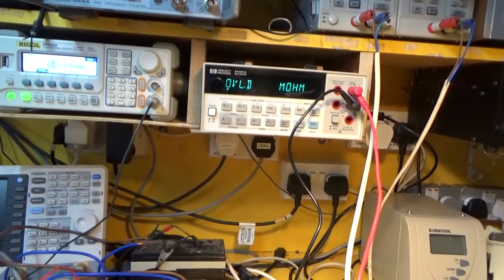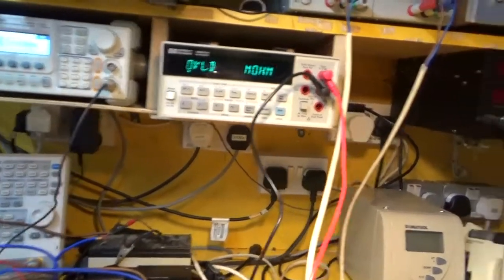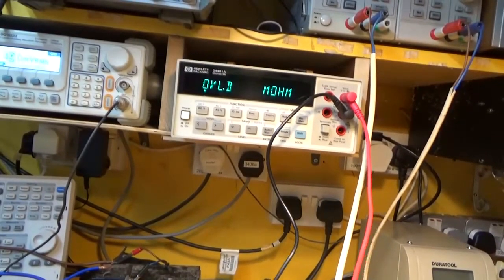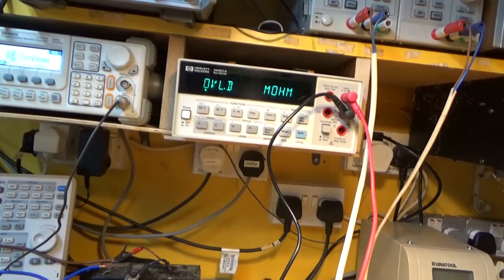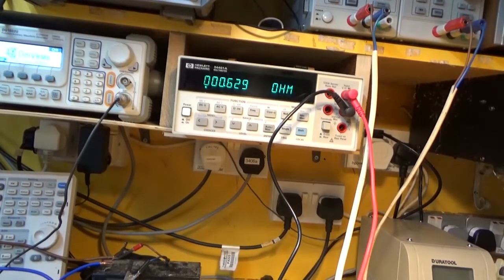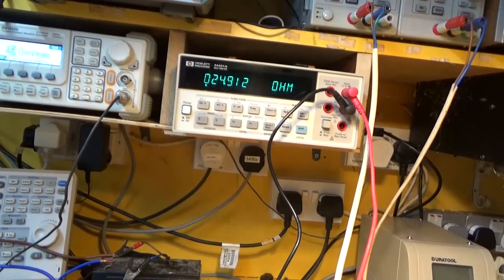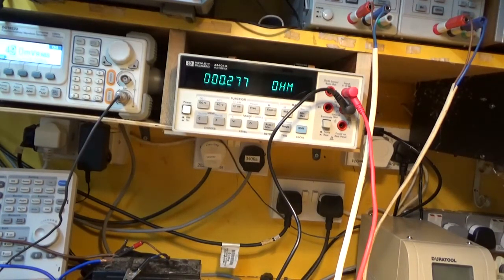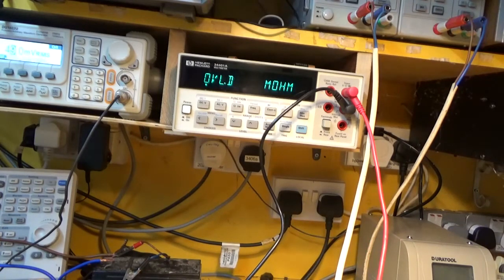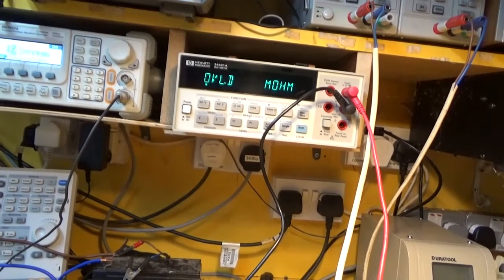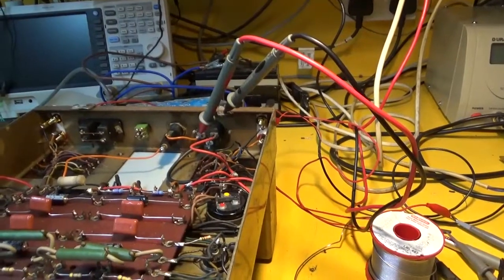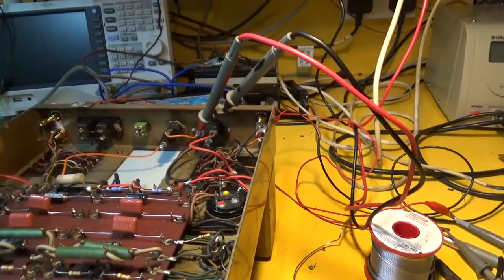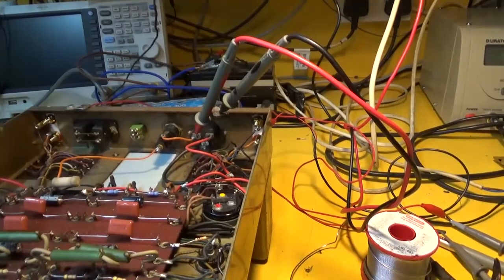So there's a bad connection on that joint. If I go over to the same point on the other channel—when I can hold the bloody thing on—these old connections are so badly tarnished, that's why there's poor connections. 0.3 ohms anyway. So I'm going to solder a link on top and see if that makes the thing work. Right then, put that link in and it works perfectly. I'm so happy that I fixed it.